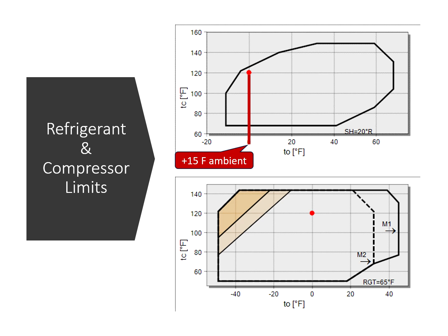It's no wonder R410A is not commonly used in food and cold storage applications, as it's not well suited for low suction temperature conditions. The second compressor map shown is for R507 refrigerant. At the same zero-degree Fahrenheit suction data point, there is a tremendous amount of room for lower suction temperatures, even below minus 20°F. This refrigerant and compressor combination is much better suited for extracting heat from very cold ambient temperatures.